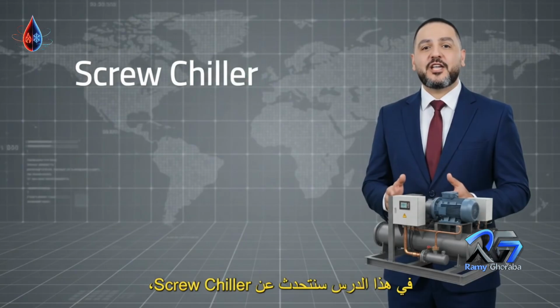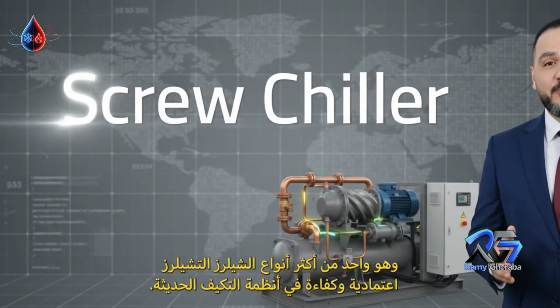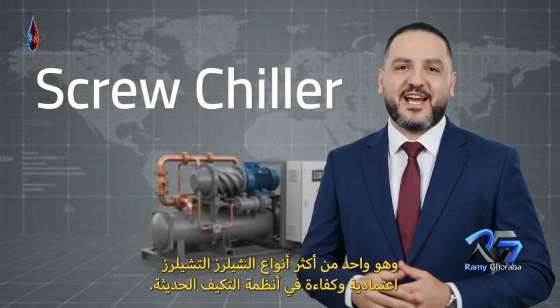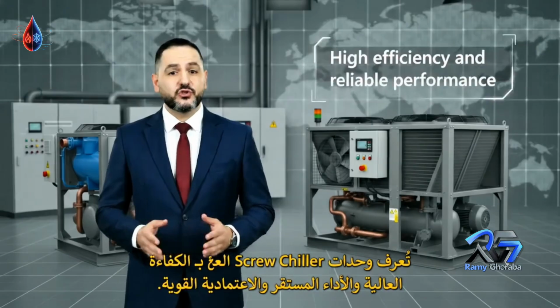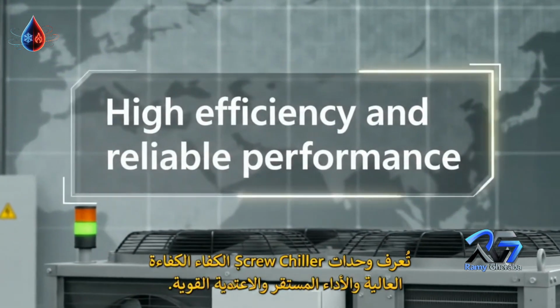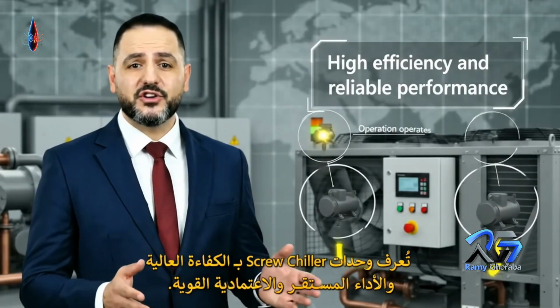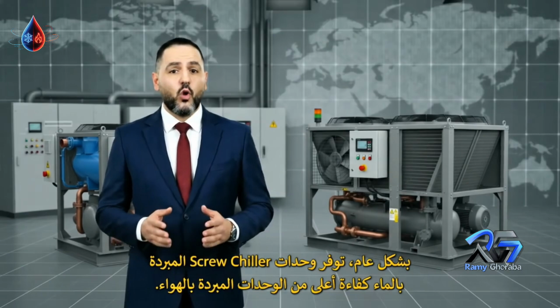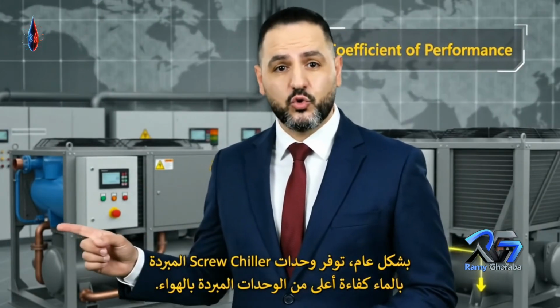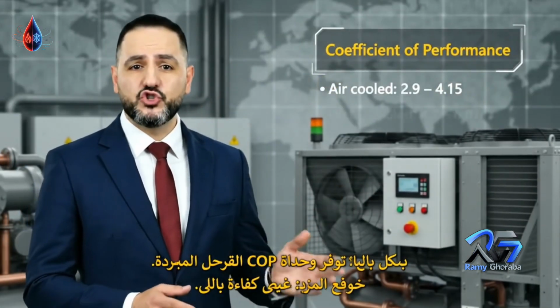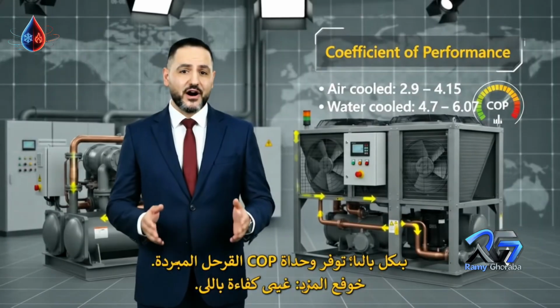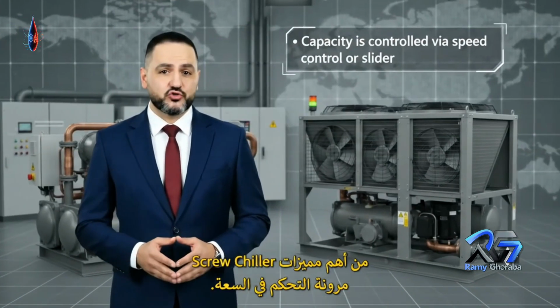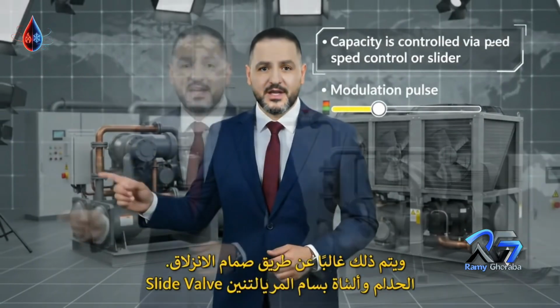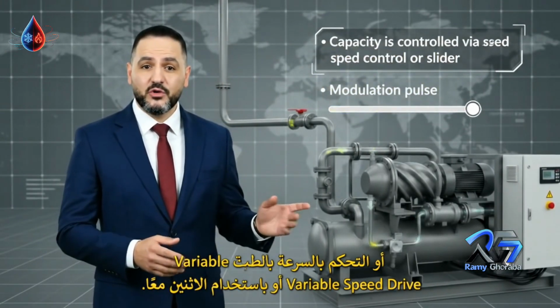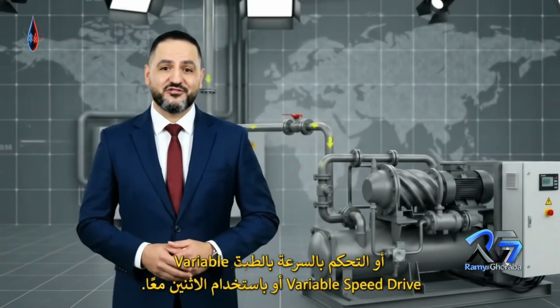In this lesson, we're talking about the screw chiller, one of the most reliable and efficient chillers used in many HVAC systems today. Screw chillers are known for high efficiency, stable performance, and strong reliability. They also handle part load operation well, which is very important in real HVAC systems. In general, water-cooled screw chillers offer higher efficiency than air-cooled ones. Typical COP values may range from about 2.9 to 4.15 for air-cooled units. One major advantage of the screw chiller is flexible capacity control. This is typically achieved by slide valve control, variable speed drive, or a combination of both.